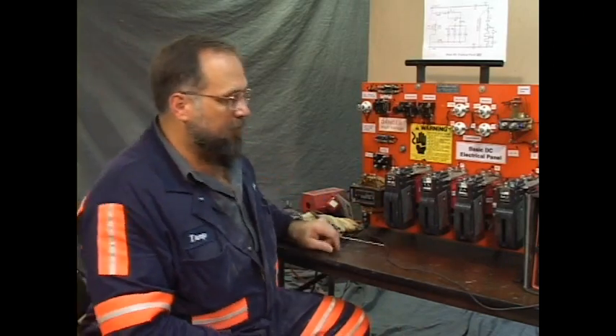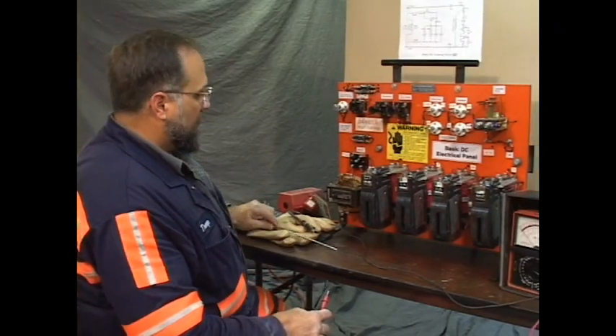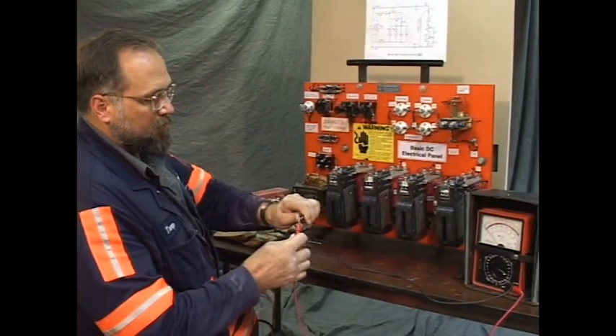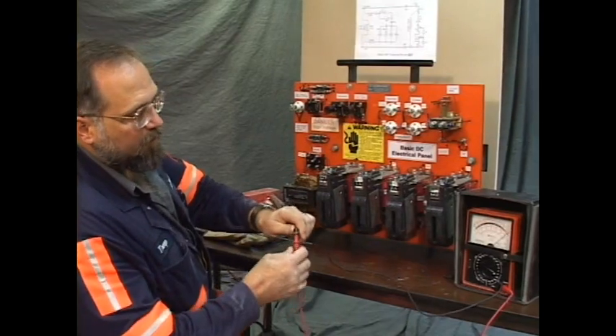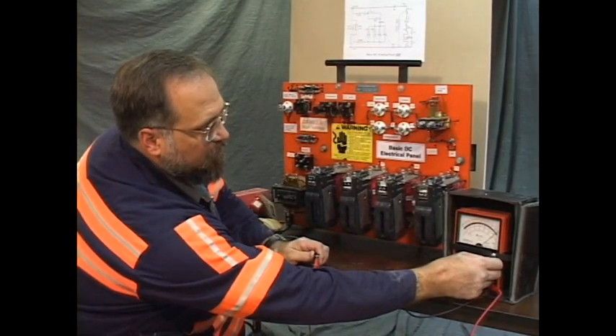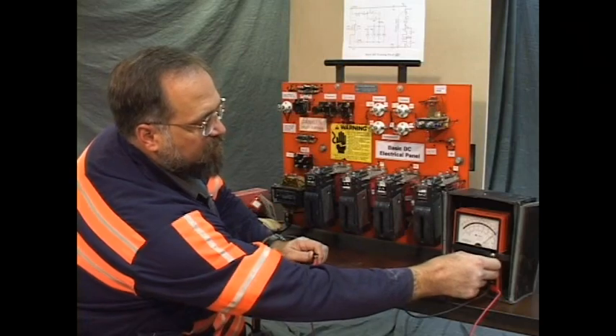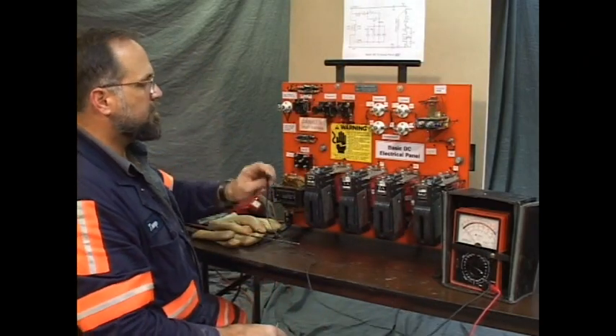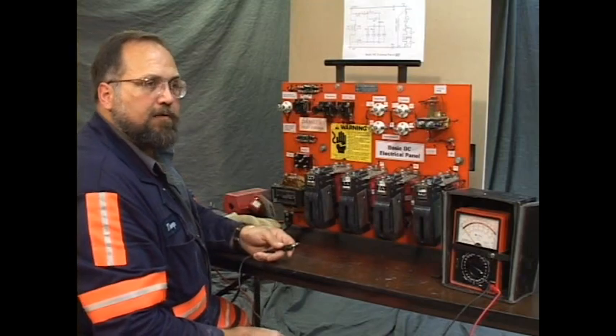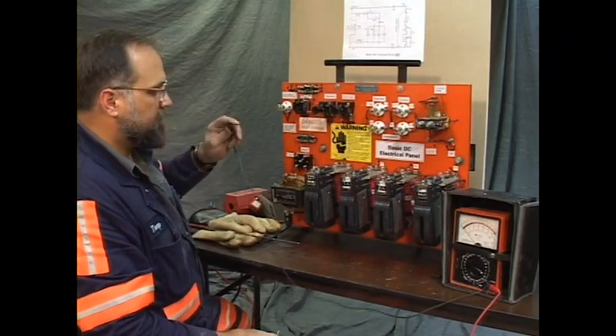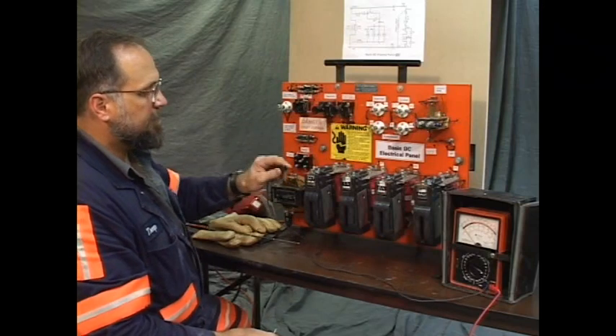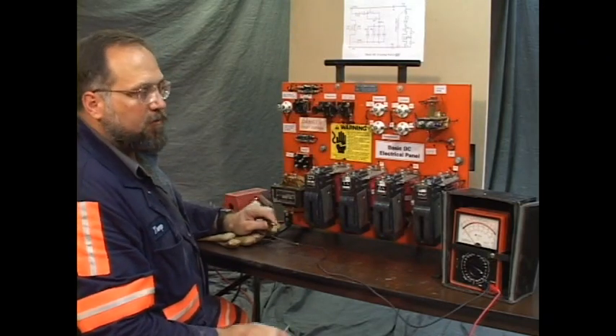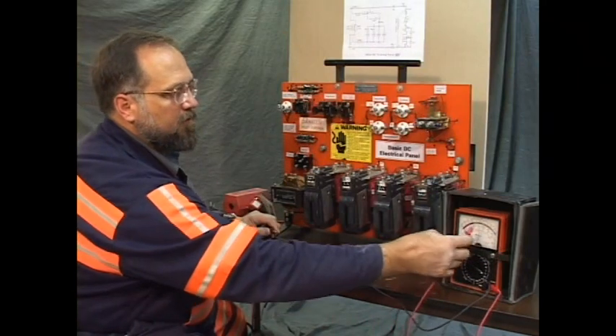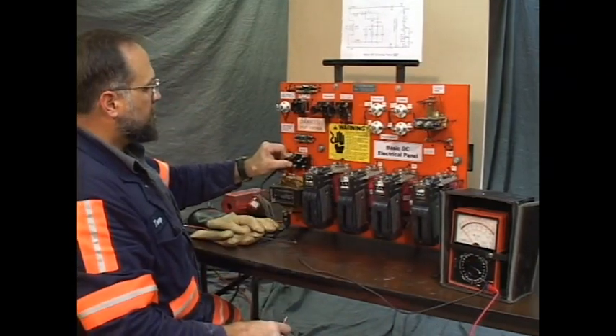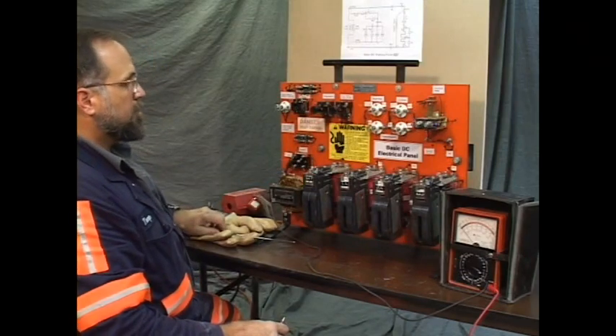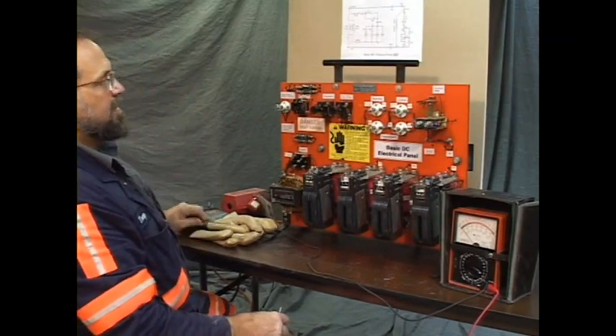So here we go. Starting at the power source, I'm going to zero this meter. We've moved about quite a bit. You'll note that some of these readings won't be completely zero. There is some resistance on every connection, every switch. There's a small amount, and checking in this fashion, we're going to make several checks in series, and those resistances will be added. So we want to always get a full scale deflection of the needle to zero. I'm going to start here at the positive terminal. You can start on either side, it doesn't matter, but you just need to be complete.